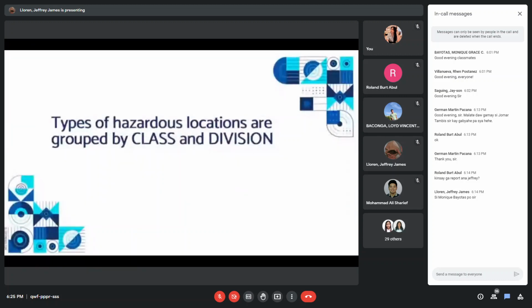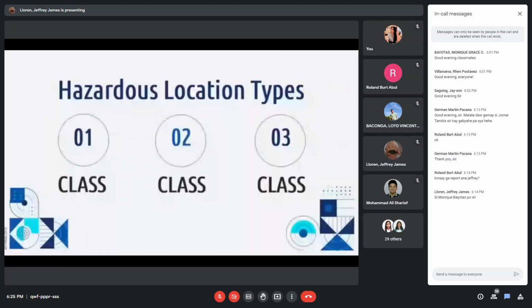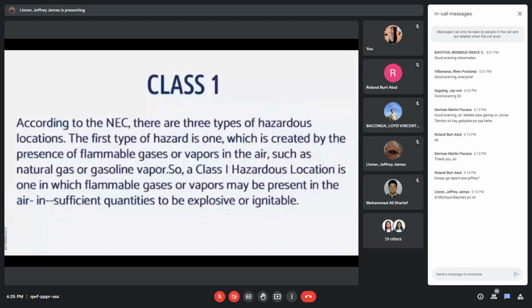Types of hazardous locations are grouped by class. So muna siya ang hazardous location types. Class 1, class 2, and class 3. Under sa class 1, according to National Electrical Code or NEC, there are 3 types of hazardous locations.